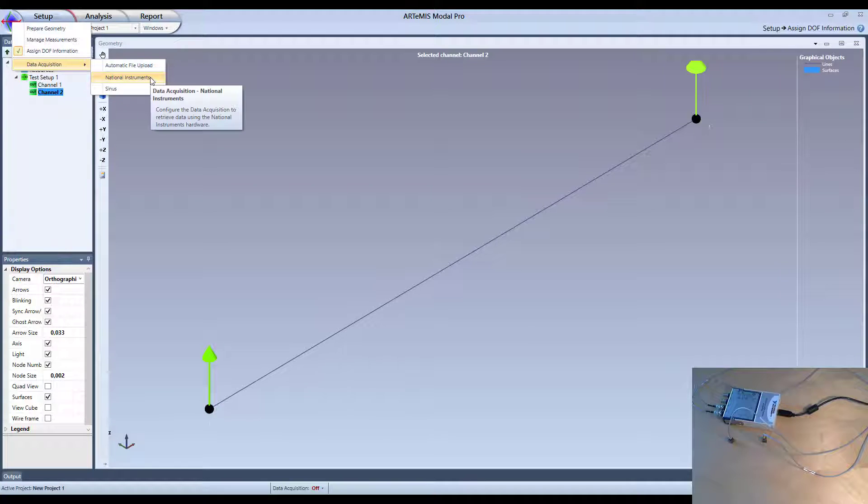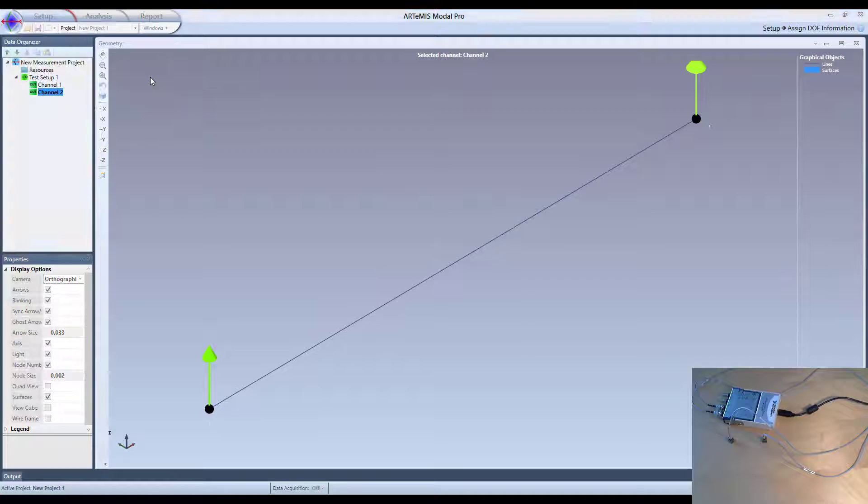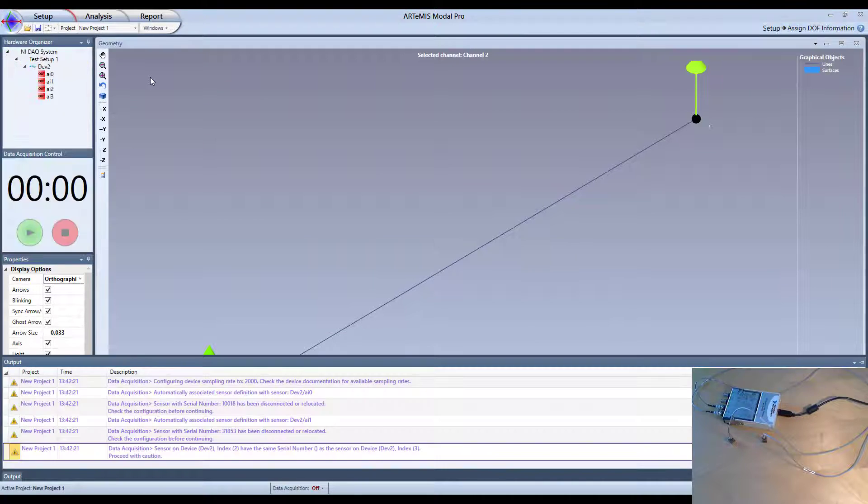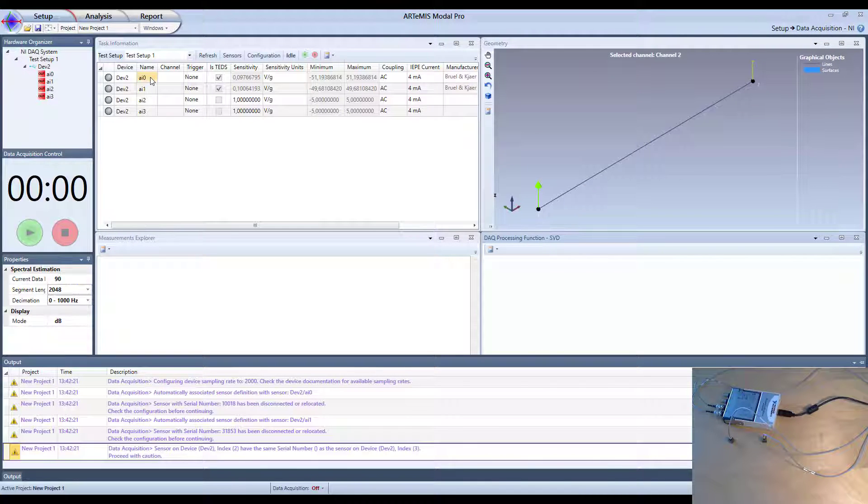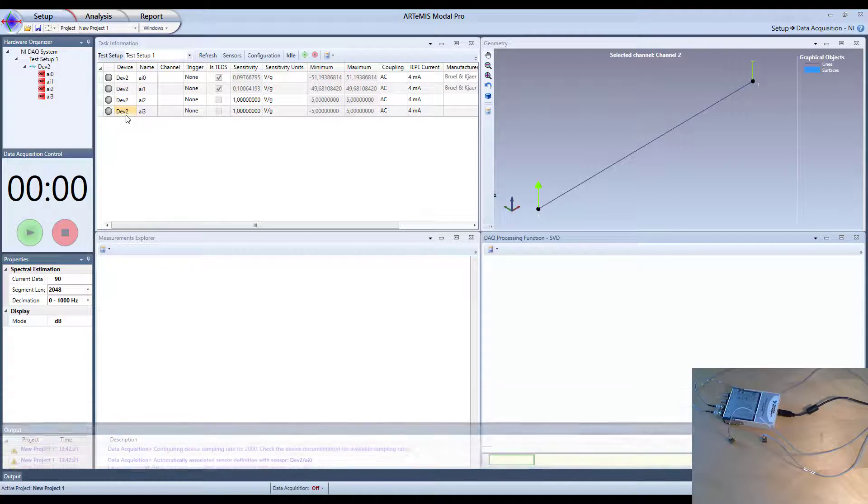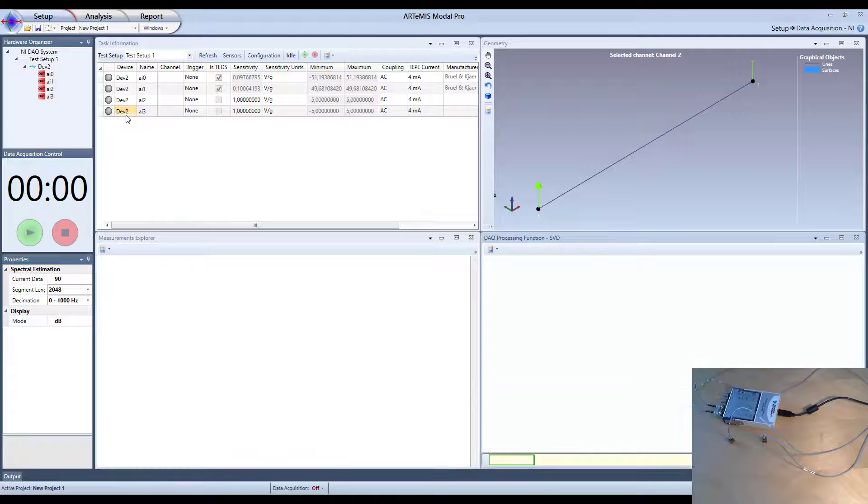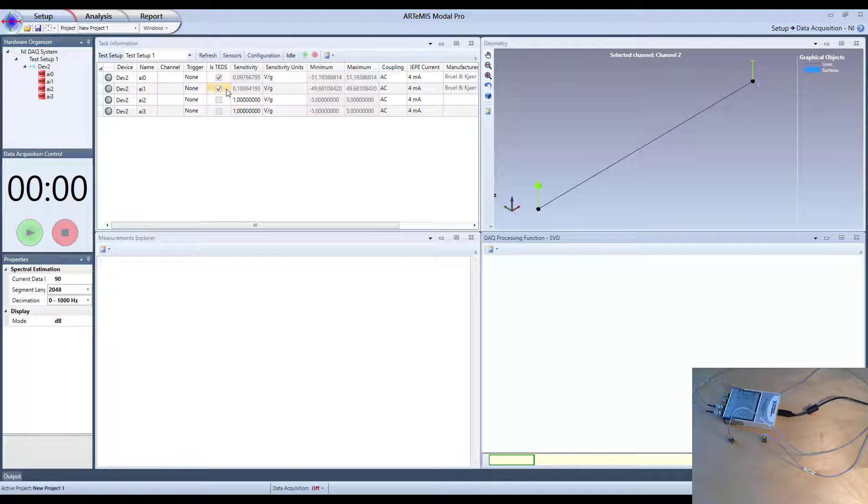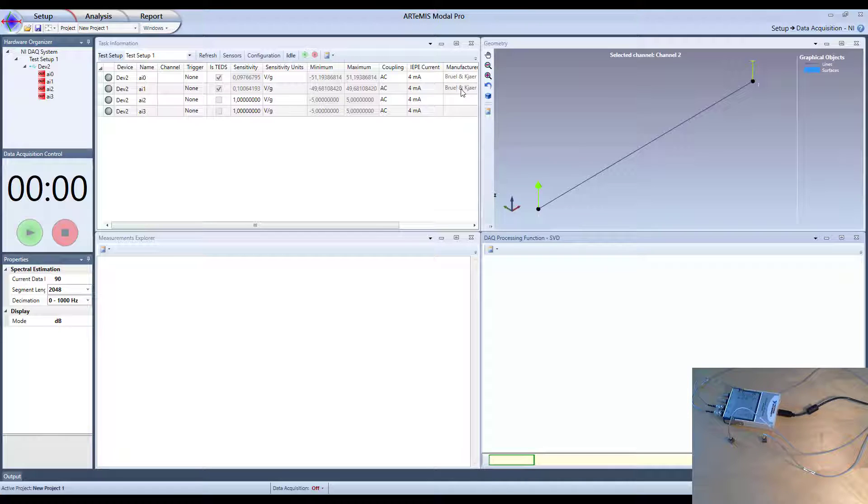And I select it here. I have different options, but I select here under setup, I select National Instruments here. And now it will then detect the instrument that has been connected. And you will see here now that we have these four channels available that we see here in the module. And we can see that already now it has detected that the two first are actually TEDS sensors being connected of the Brüel and Kjær type also.